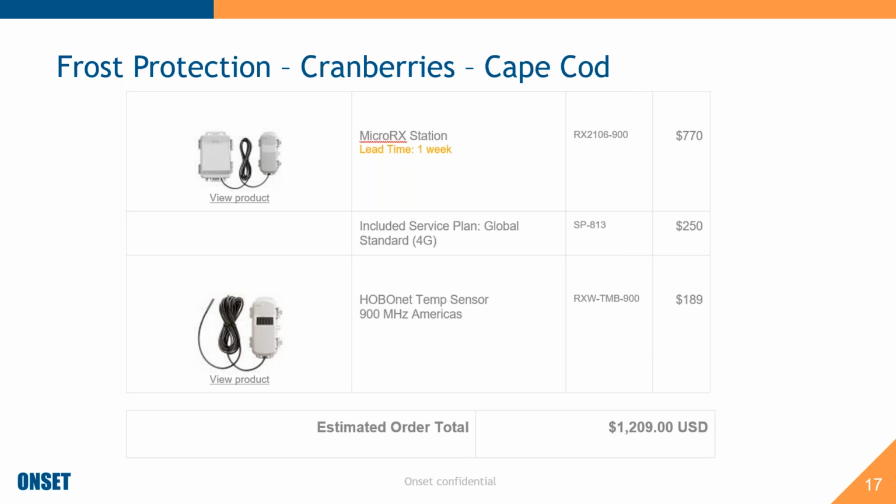And Rich, I'm going to throw in a question here. Somebody had a question about temp loggers being used in the solar radiation shield. And the question is, during the day, the temp values will be higher than the real temp. Just going back to a couple slides ago, if you're wanting an accurate daytime temperature, we definitely recommend one temperature sensor being used inside a solar radiation shield, and then an additional sensor that you would kind of ignore during the daytime, because that one's going to heat up with the sun, but at night it's actually going to provide a faster response time. Hope that answers the question there.